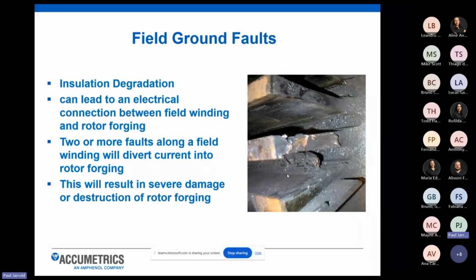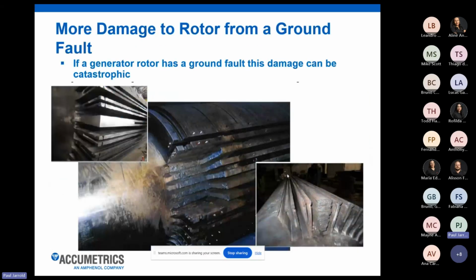So it's a massive cost to utilities, because not only are you not creating power to provide to the grid and essentially to sell your electricity, you're also having to pull your machine down in an unplanned outage, and that can cause a massive amount of cost to the utilities. So again, two faults are the most severe case, and that can result in the biggest amount of damage. However, a single point fault can also be damaging, like I showed where the fault happened underneath the retaining ring.